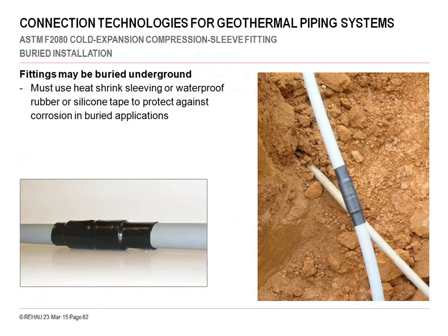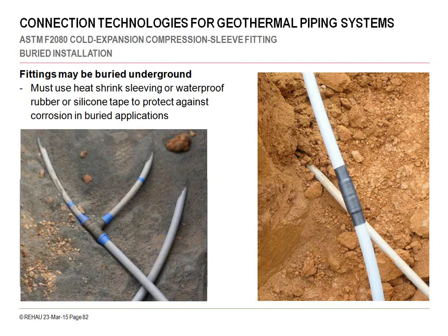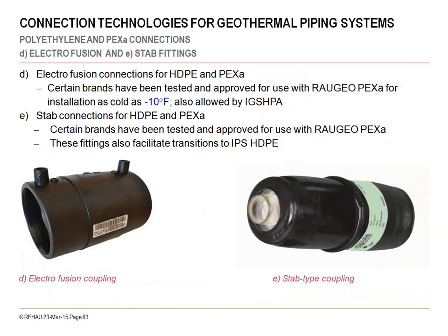And as mentioned, we want the fittings to be protected with a heat shrink sleeve or waterproofing tape. And here's waterproofing tape you can see in the image on the left with some branch tees. And as mentioned, the other two methods for PEX-A would be electrofusion couplings and stab fittings. The stab fittings you can think of almost like a SharkBite. On either side of that stab fitting, there are two O-rings, and the PEX-A pipe gets chamfered down about 1/8 of an inch, and then when you insert it, it goes underneath those O-rings. So you've got those two O-rings on the OD of the pipe, which is where you want to see it, just because with any polymer material, with temperature changes, you're going to get some slight expansion and contraction. You've got the seal of the O-rings going with it.